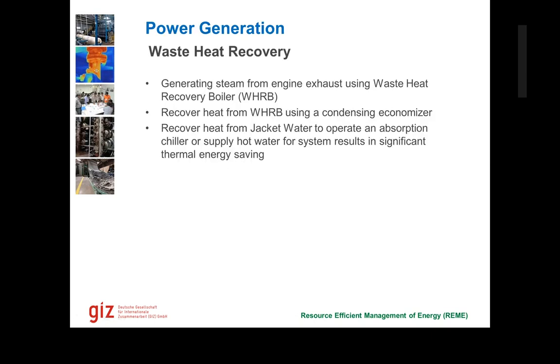Then power generation. I hope you are well aware of the heat recovery potentials in the power generation system, where we can recover heat using a waste heat recovery boiler. We can install another condensing economizer or a simple economizer on top of a waste heat recovery boiler to recover further heat, so heating up water for process. Then the jacket water or engine cooling water can also be used to operate absorption chillers or to supply hot water for the processes that bring in significant thermal energy savings.